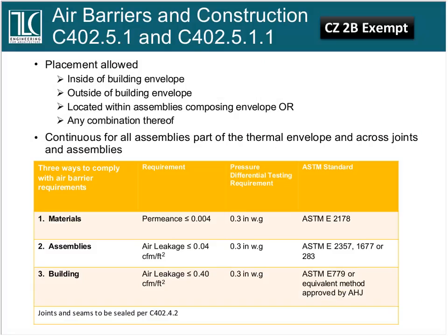This air barrier requirement goes throughout all of the climate zones except for 2B, the desert Southwest. And there are 3 ways to comply with the air barrier requirement. One is to make your building envelope out of nothing but materials that meet the ASTM E2178 permeance standard. Or you can construct the envelope out of assemblies of materials that have been tested by these 3 ASTM standards. Or you can make it out of anything you want to, as long as you can pressure test the building to show that it doesn't leak more than 0.4 of a CFM per square foot of building envelope area when subjected to a 0.3 of an inch of water gauge pressure difference on the building envelope.